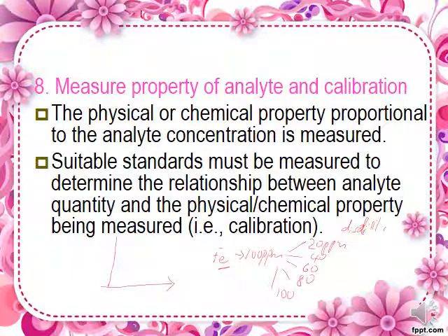Okay, so let's say you use distilled water to prepare this standard solution. So the distilled water only will become the blank. So of course the blank will have 0 ppm. So this is the ppm. This is the absorbance of the AAS instrument. Okay, AAS. So you must have a straight line. Okay, standard calibration curve. Okay, so this is 20, 40, 60, 80, 100 ppm. So probably you get somewhere here, somewhere here, somewhere here, here. Okay, it's line of best fit.